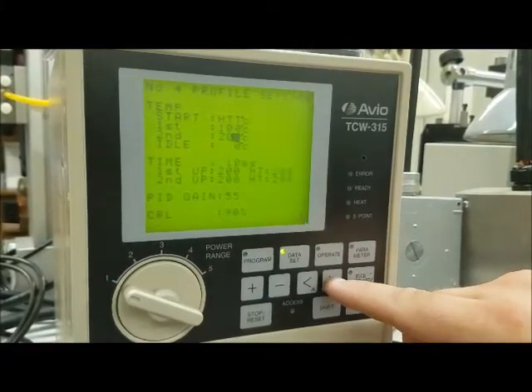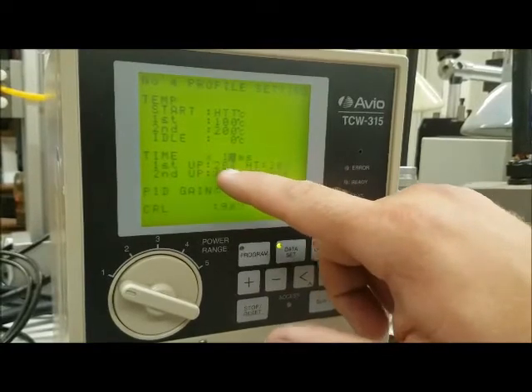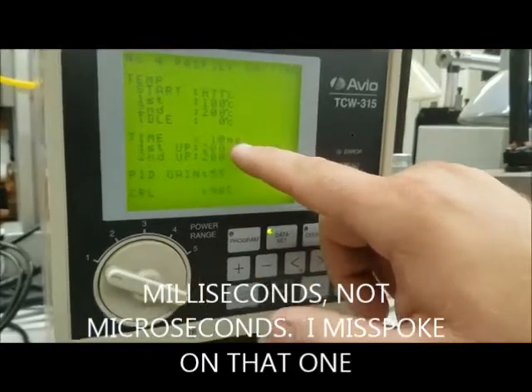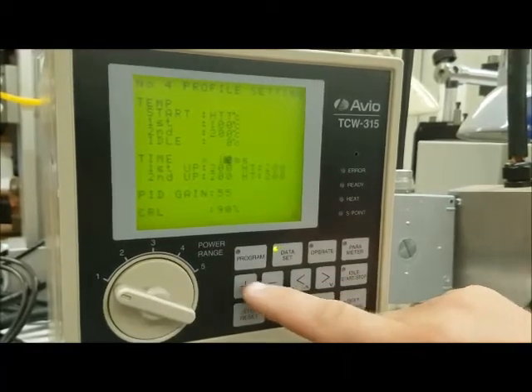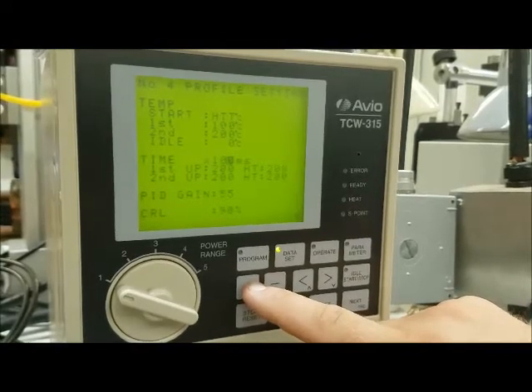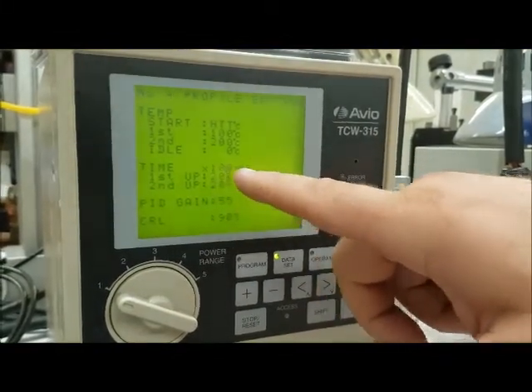Going down here is the second temperature, 200 C. This is a time setting. Whatever these numbers are gets multiplied by what you put here. In this case it's 10 milliseconds. If you wanted to change it to 100 milliseconds, you push the plus button. This multiplies your number of seconds, so you can go from 2 seconds to 20 seconds by changing that from 10 to 100.